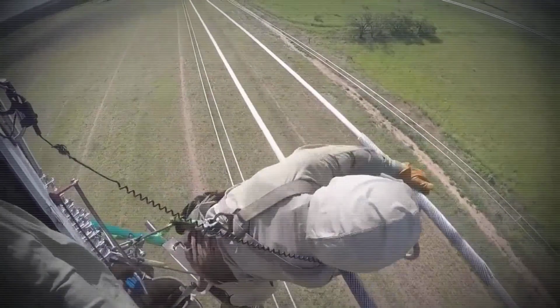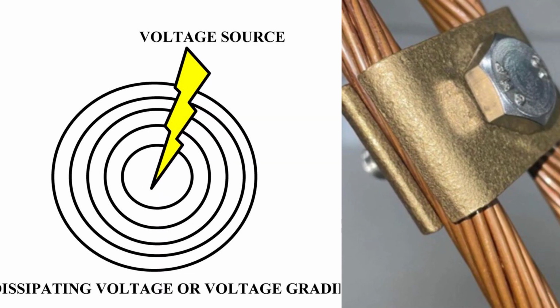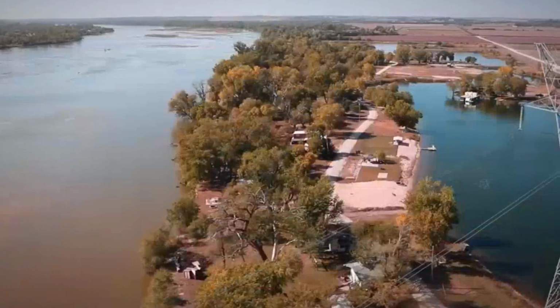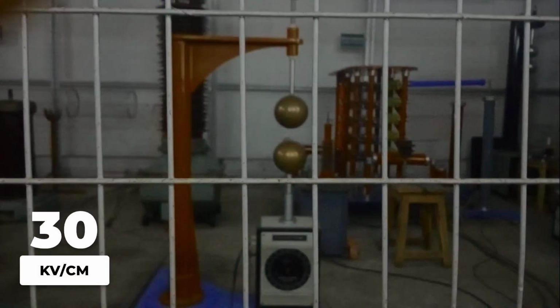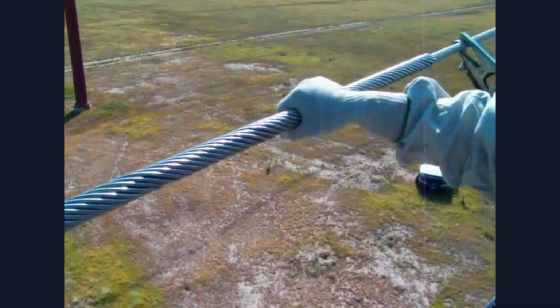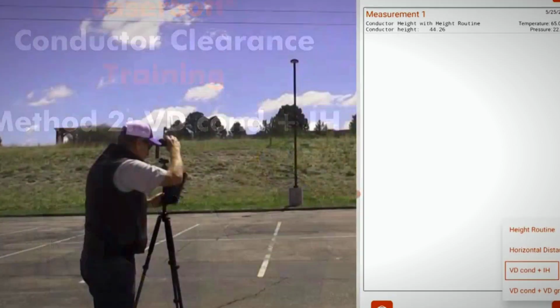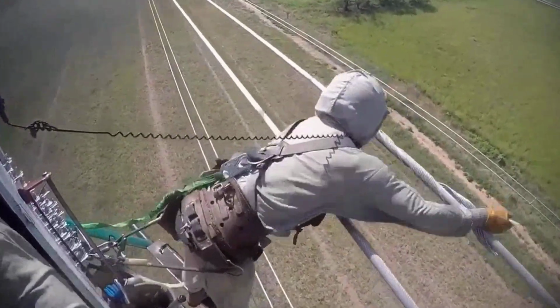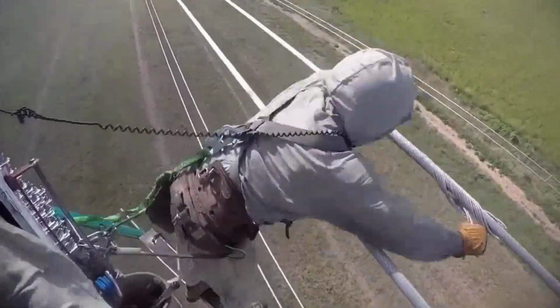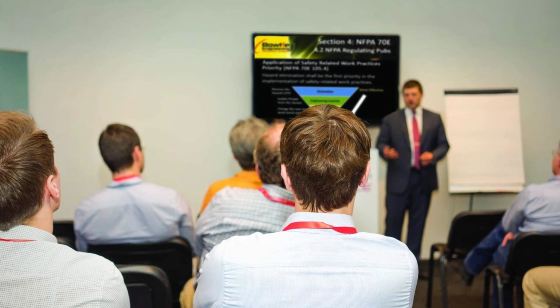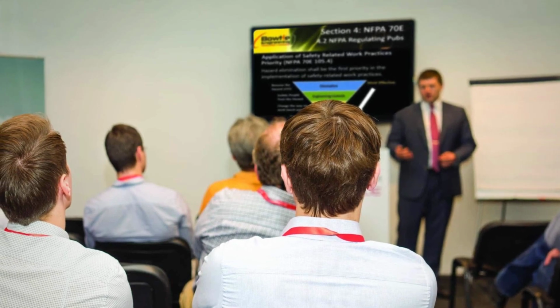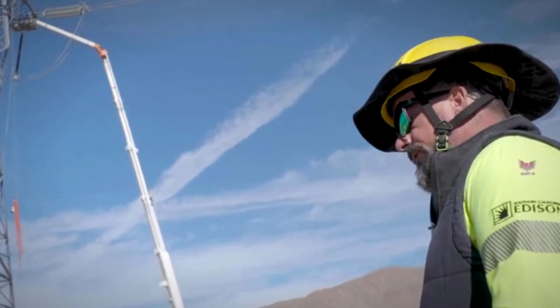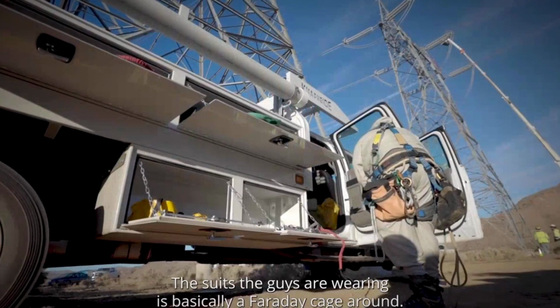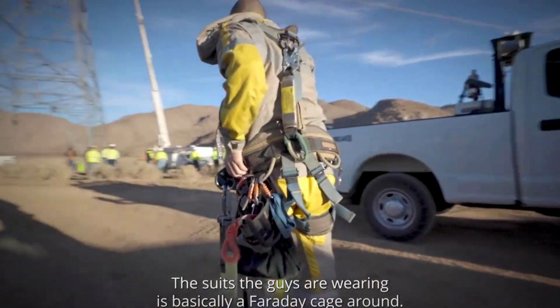The bond must remain unbroken. Any interruption can create a dangerous voltage gradient. Air itself acts as a barrier. Dry air's dielectric strength is about 30 kilovolts per centimeter. For 115 kilovolt lines, the minimum safe gap is 38 centimeters. For 345 kilovolt lines, it is 115 centimeters. Standard clearances, enforced by OSHA and NFPA 70E, add safety margins up to 180 centimeters for the highest voltages.